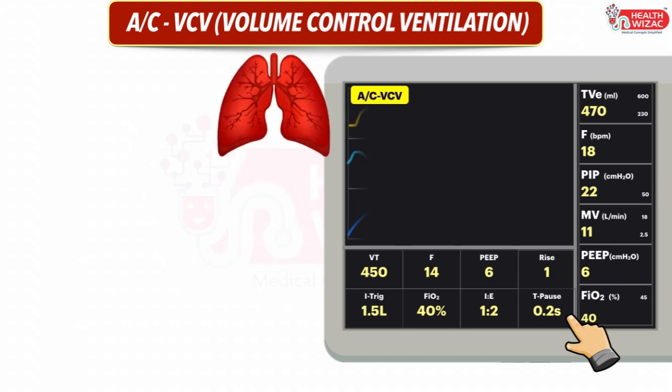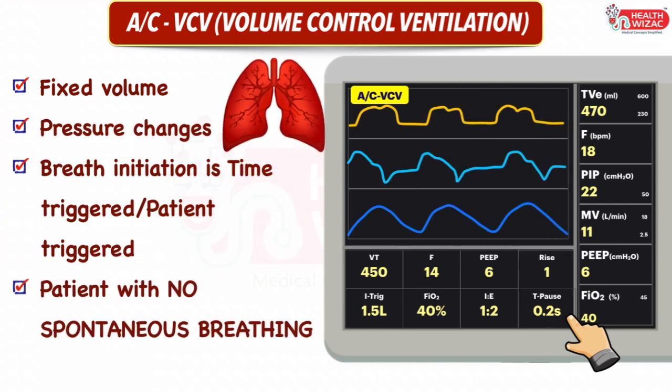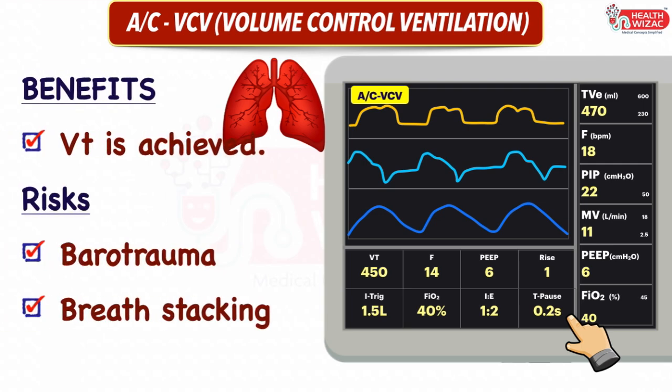In Volume Control Ventilation, the volume of air delivered per breath is fixed. Pressure changes as per flow trigger or inspiratory time and lung condition. Breath initiation is time-triggered in control mode and patient-triggered in assist mode. It should be used when the patient has no spontaneous breathing, or the patient should be sedated and paralyzed. Advantages include delivery of desired tidal volume, whereas disadvantages include barotrauma — as pressure may increase if resistance increases and lung compliance decreases — and breath stacking.